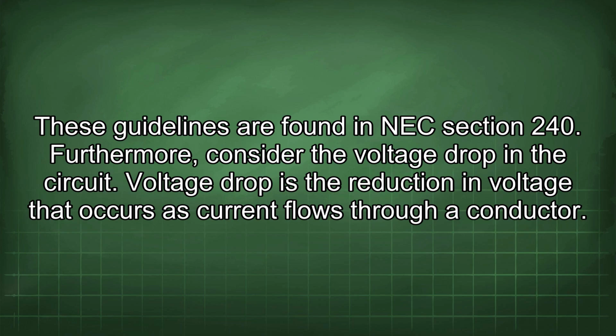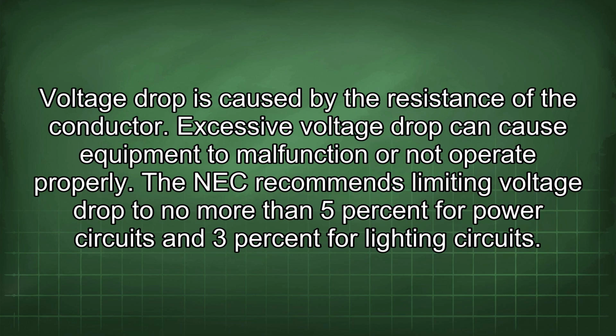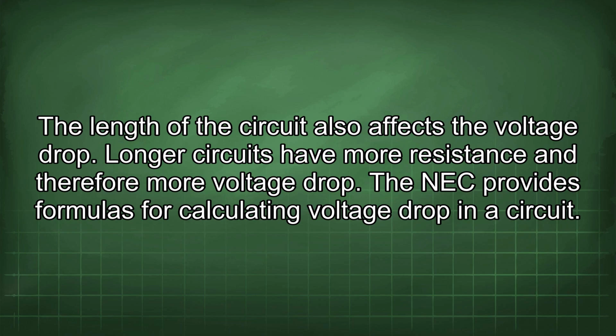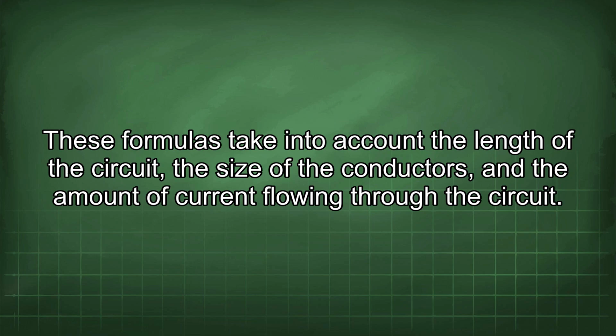Furthermore, consider the voltage drop in the circuit. Voltage drop is the reduction in voltage that occurs as current flows through a conductor. Voltage drop is caused by the resistance of the conductor. Excessive voltage drop can cause equipment to malfunction or not operate properly. The NEC recommends limiting voltage drop to no more than 5% for power circuits and 3% for lighting circuits. The length of the circuit also affects the voltage drop. Longer circuits have more resistance and therefore more voltage drop. The NEC provides formulas for calculating voltage drop in a circuit. These formulas take into account the length of the circuit, the size of the conductors, and the amount of current flowing through the circuit.